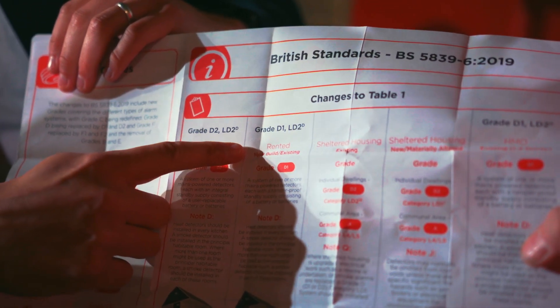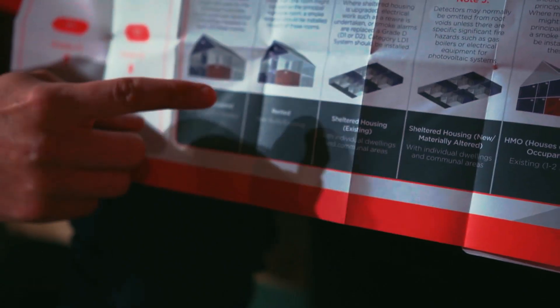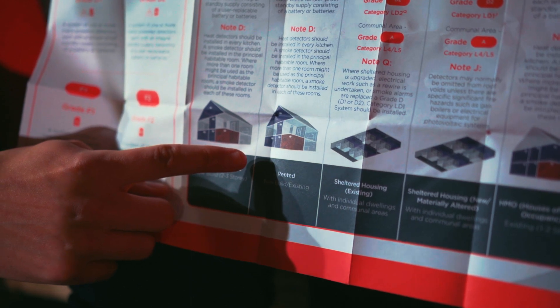That ties in with changes to BS 5839 part six 2019, which replaced the 2013 update and covers domestic installation of fire and smoke alarms. Up until May 2019, it just said 'grade D' — mains powered with a form of battery backup. The May reclassification went into more detail: grade D1 has tamper-proof battery backup, and grade D2 has a user-replaceable battery.